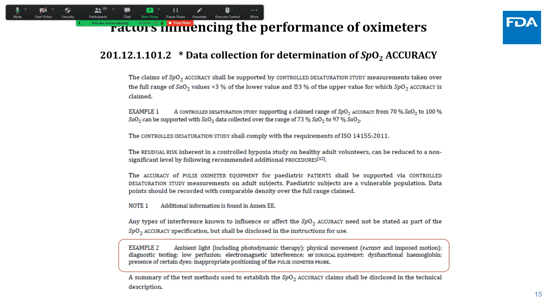And no discussion of oximetry would be complete if we didn't open up the table to the research possibilities. As Mike alluded to, there are lots of issues out there, not the least of which is what statistic we should be using to report the performance. We've been using the root mean square error because it's a combination of the bias and the precision that gives you, the clinician, a single index, which we thought was digestible and which industry and clinicians have been using for, I'll say, decades. But maybe that needs to be fixed. Maybe there's additional information, and clearly we have a problem with reporting on pigmentation. That needs to be fixed. And just figuring out how to objectively measure pigmentation has turned out to be much more complex than just slapping a scale on it or something.